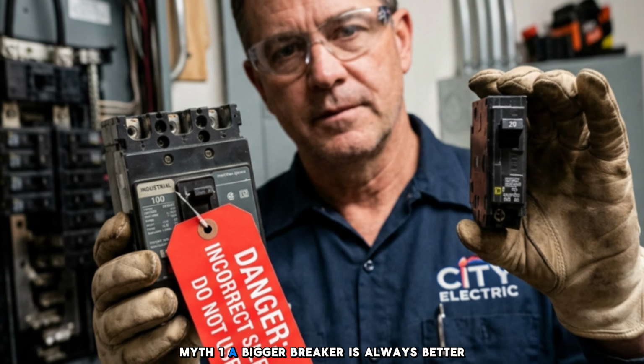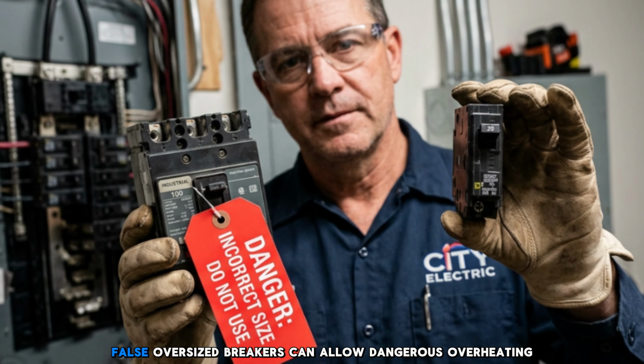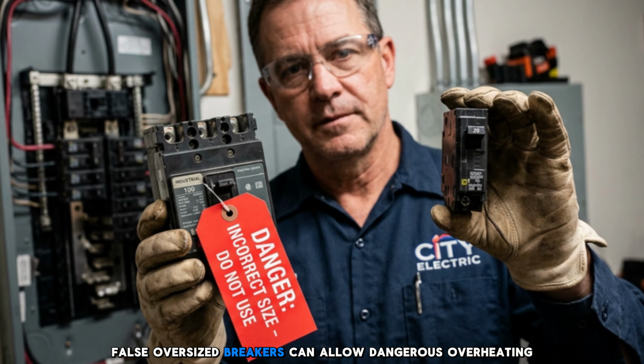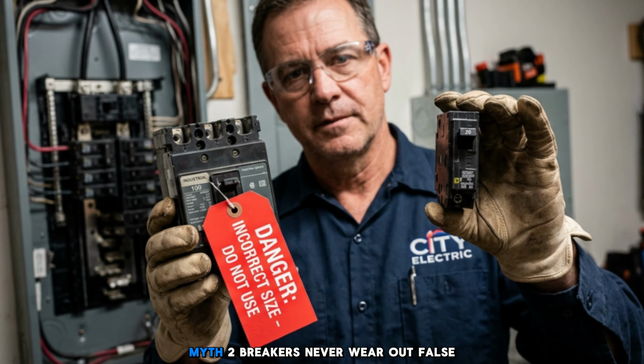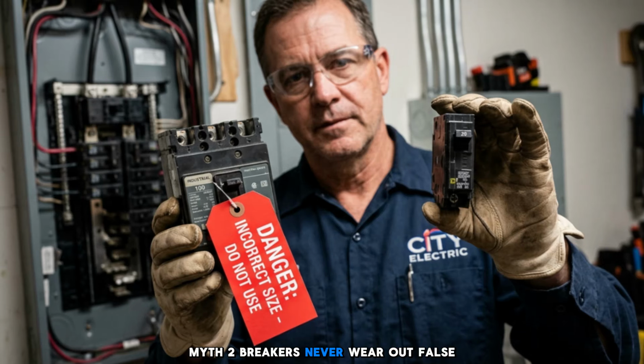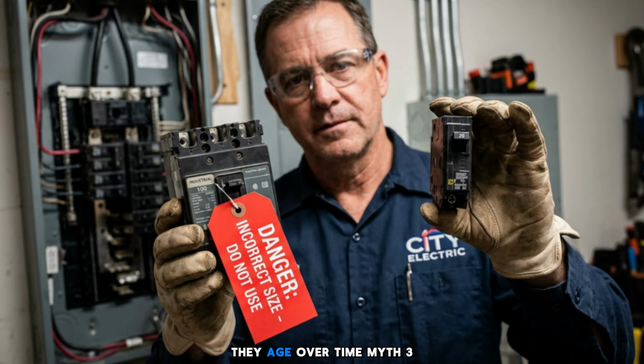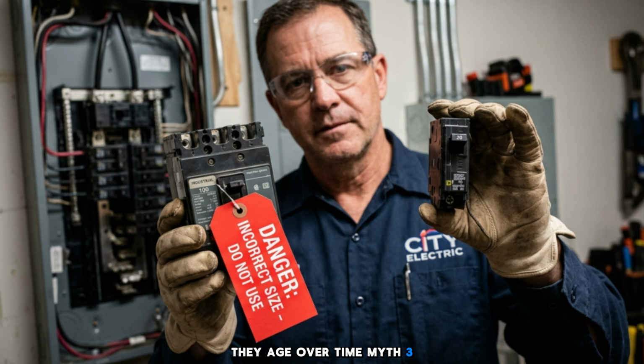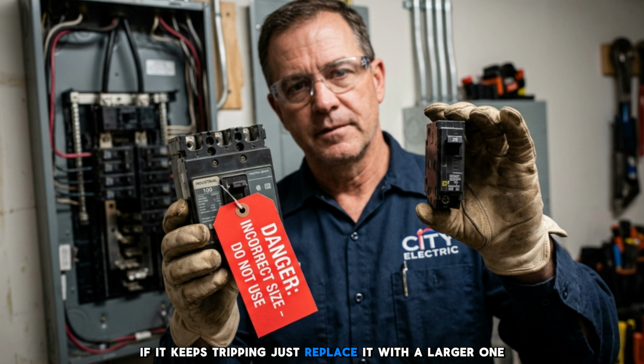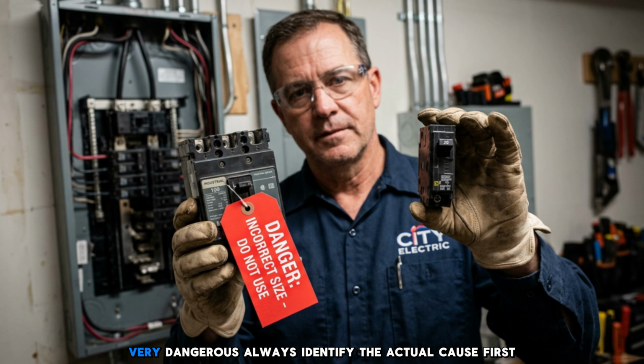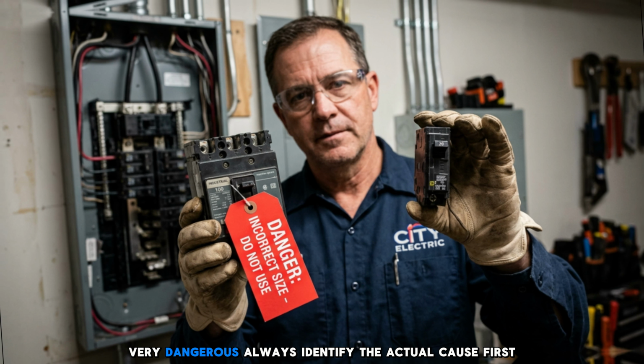Myth 1. A bigger breaker is always better. False. Oversized breakers can allow dangerous overheating. Myth 2. Breakers never wear out. False. They age over time. Myth 3. If it keeps tripping, just replace it with a larger one. Very dangerous. Always identify the actual cause first.